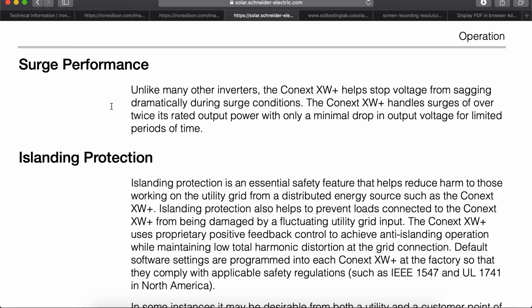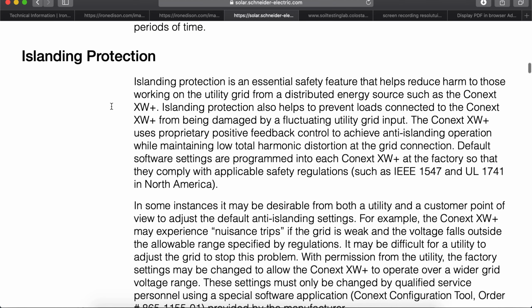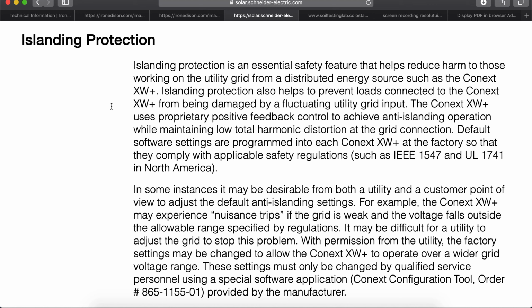Let's learn a little bit about the surge performance of the Conext XW Plus inverter. Unlike many other inverters, the Conext XW Plus helps stop voltage from sagging dramatically during surge conditions. The Conext XW Plus handles surges of over twice its rated output power, with only a minimal drop in output voltage for limited periods of time. This is helpful when starting an air conditioner or running a well pump, both of which are becoming more and more prevalent in full off-grid systems.